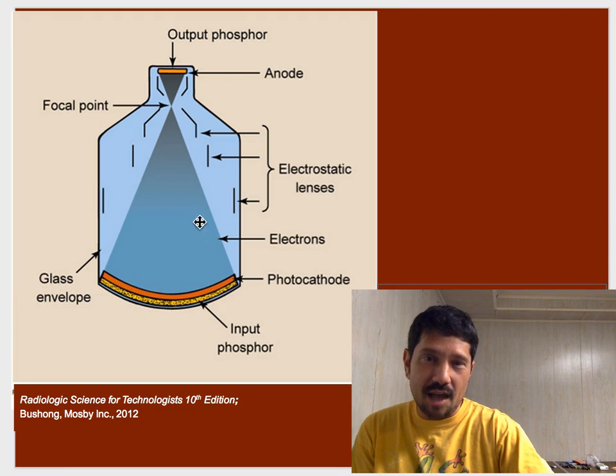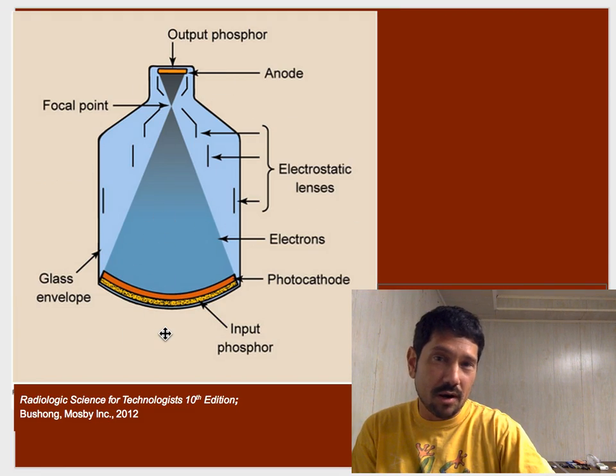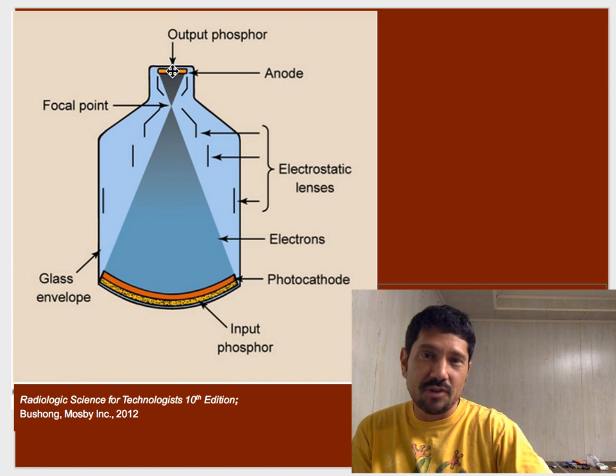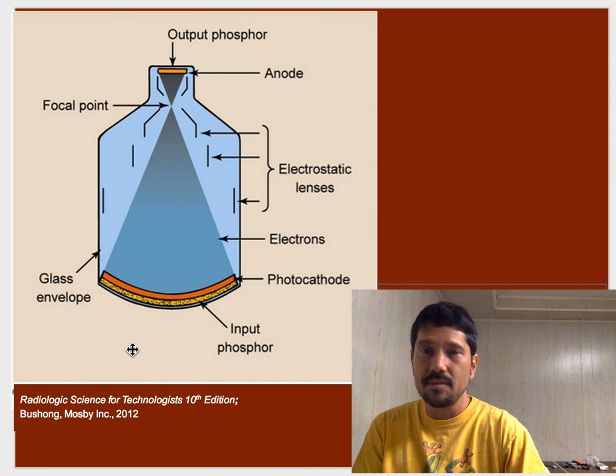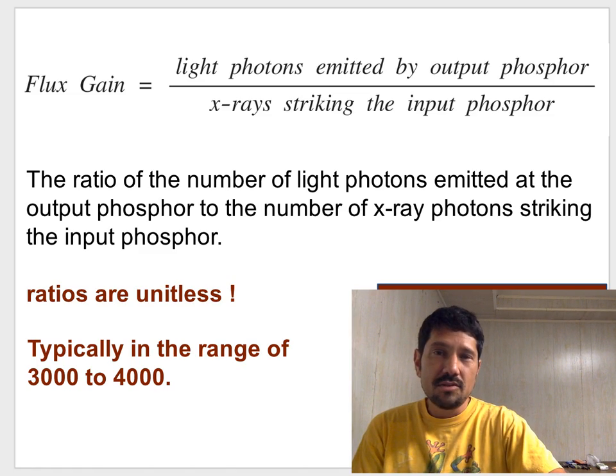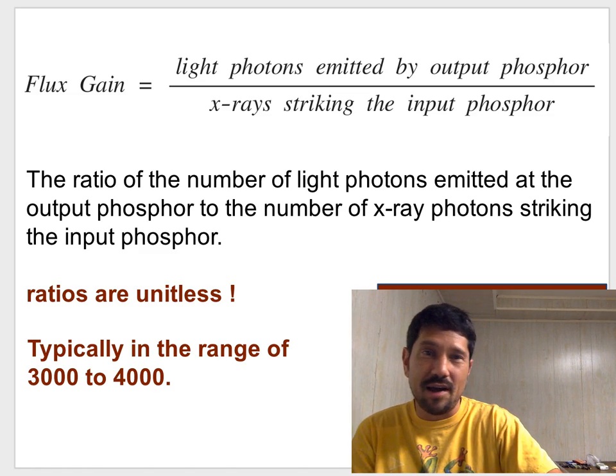When it's packaged up, of course, it looks like our big jug of water. And here's our output phosphor, typically around an inch. And here's our input phosphor that you'll find maybe 9 inch, 10 inch, 12 inches. So that flux gain is light out over X-rays in.